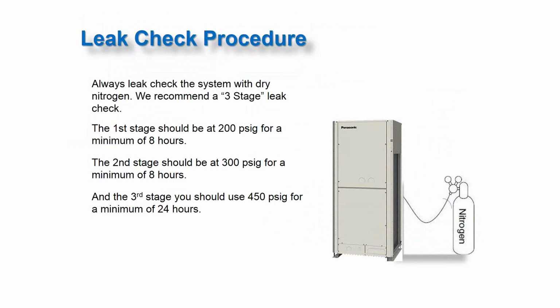So what we do is we do a 3-stage leak check. We pump the system up with nitrogen to 200 pounds and we leave it for 8 hours. After that, we pump it up to 300 pounds and we leave it for another 8 hours. And then the 3rd stage, we pump it up to 450 pounds and we leave that for 24 hours. It is a bit time consuming, but when you're doing a large installation in a large building, this is a corner that you just cannot cut, because dealing with leaks at some point in the future is very, very, very problematic.